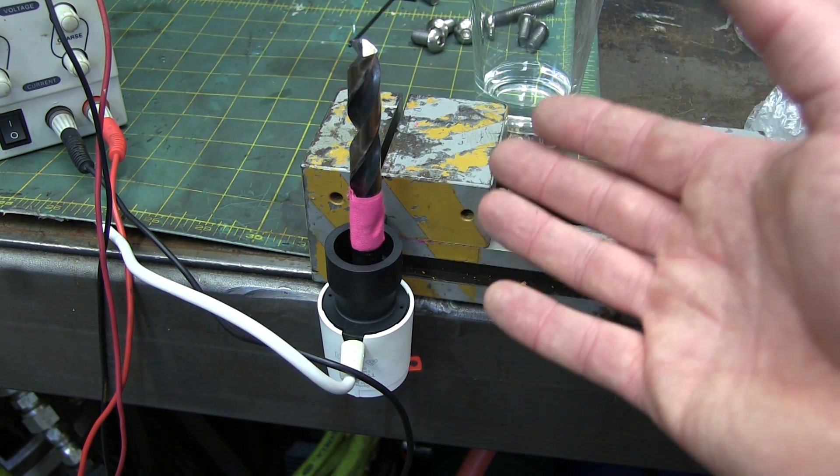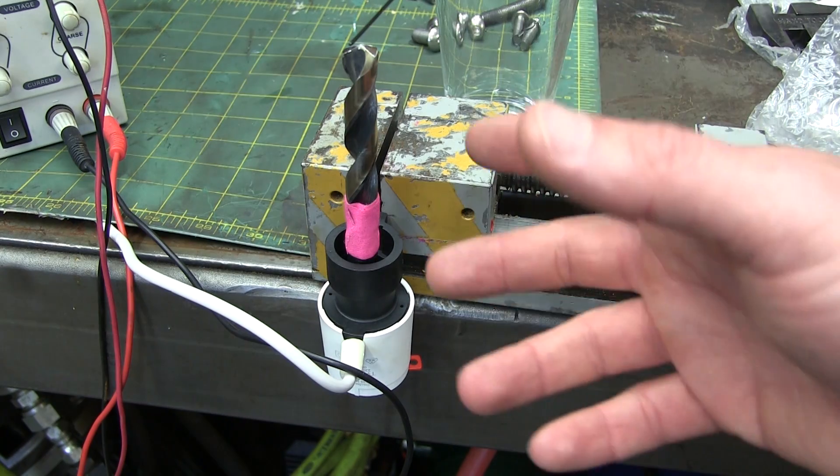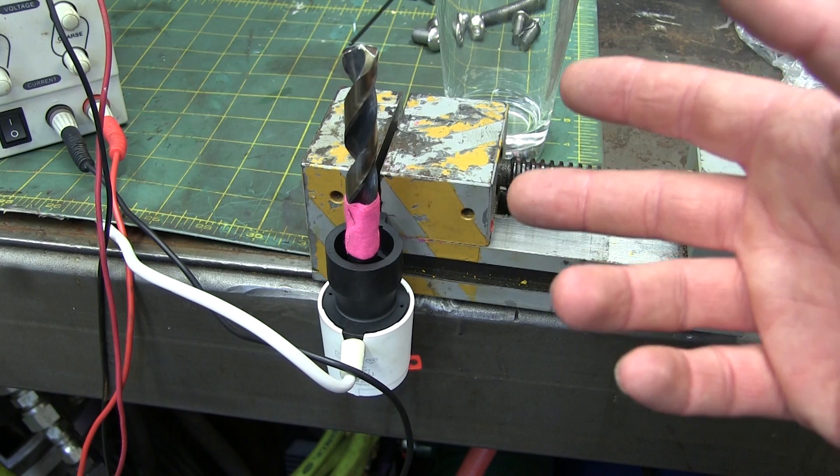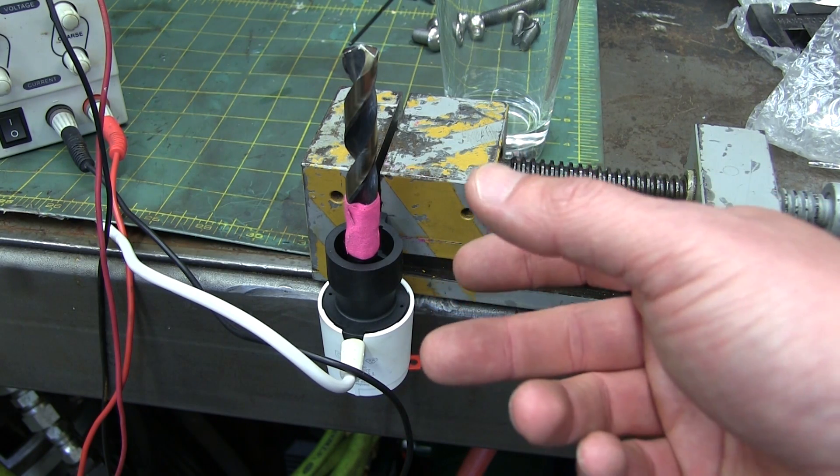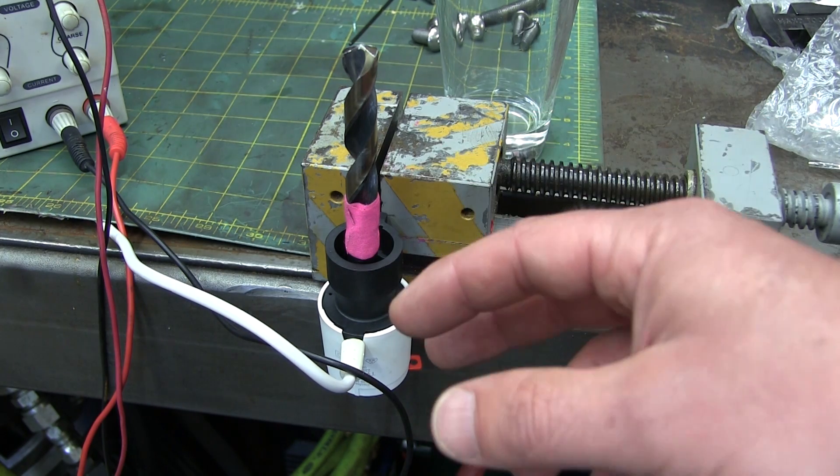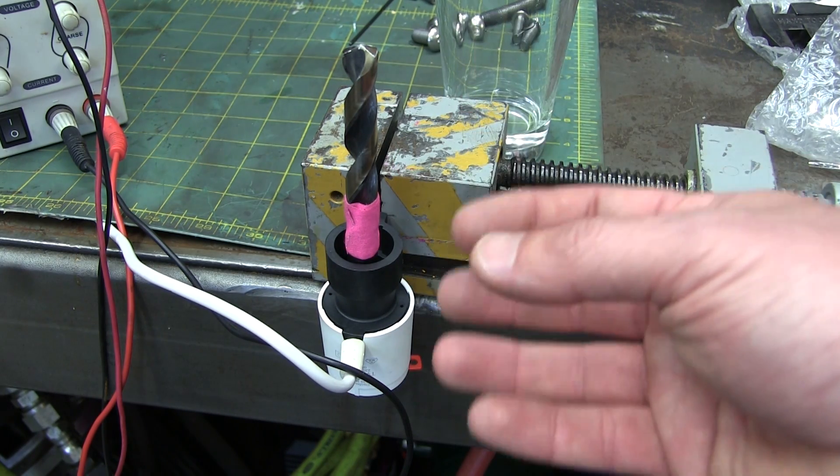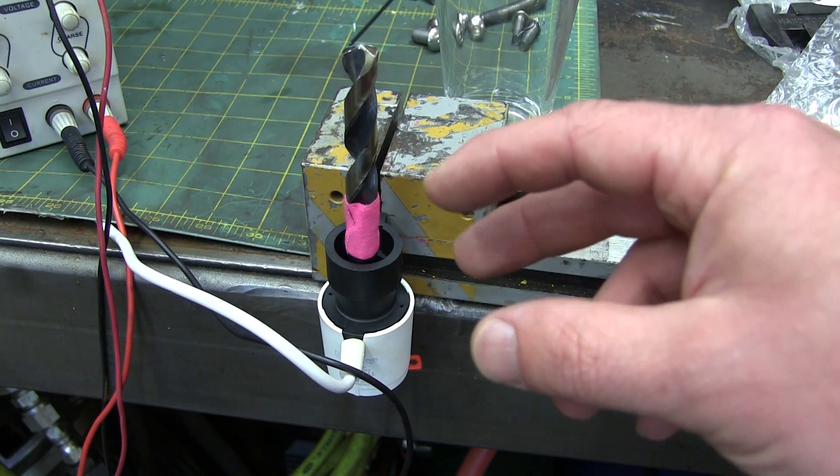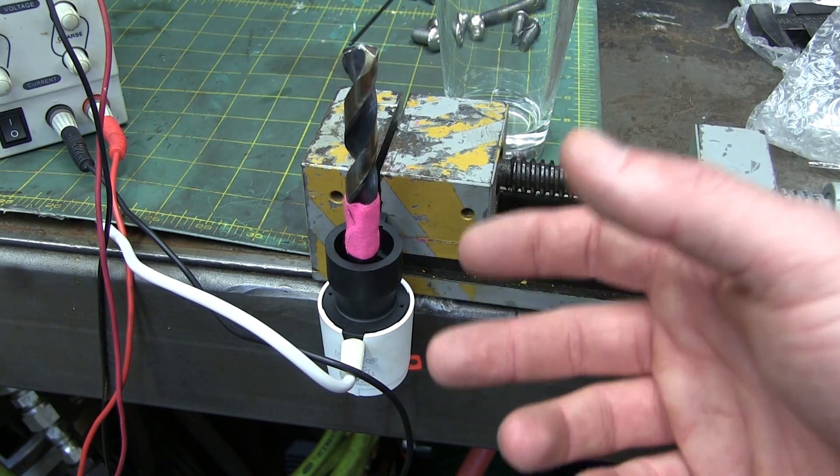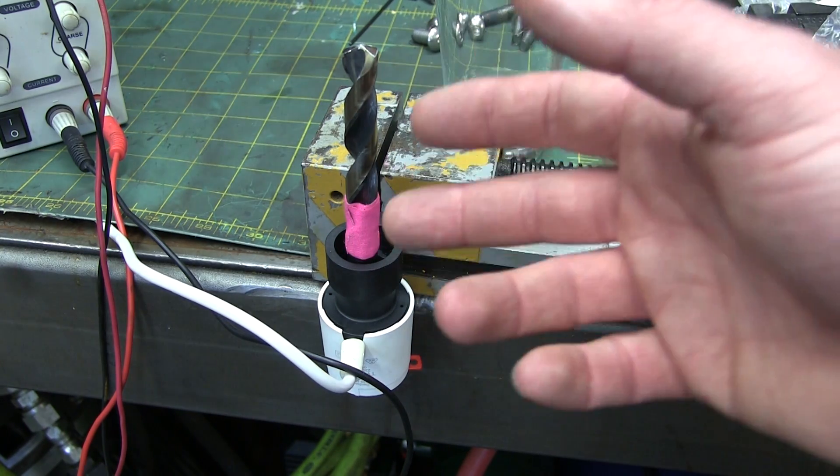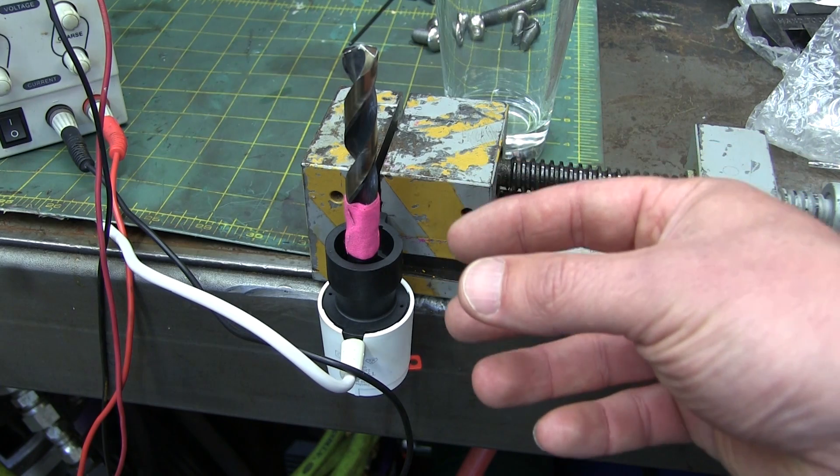It's quite amazing to me how simple this really is. Essentially you pick the right material and it does the work for you. Now it occurs to me this is very very smart as well because it's slow actuation. So it's slow to actuate in one direction, there's a bit of hysteresis there, difference in temperature between actuation and retract and extend. But also because there's a high latent heat capacity in that paraffin it doesn't slam on or off. It eases on or off. So you got a heating system with steam or hot fluid in there, that is a very good innate feature. You couldn't get this valve to slam on and off if you tried because you got to take the heat out of that paraffin and that takes a while, so nice smooth actuation.